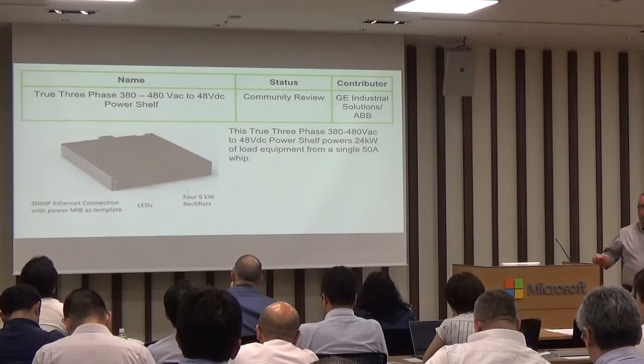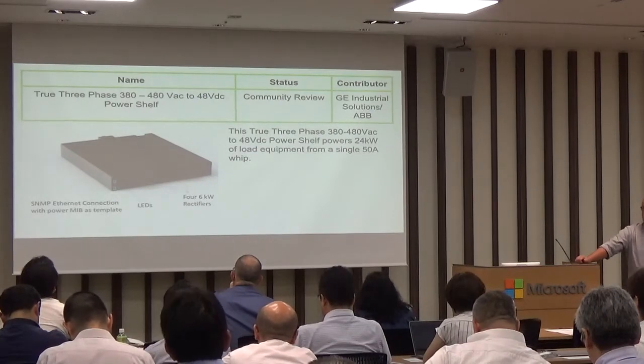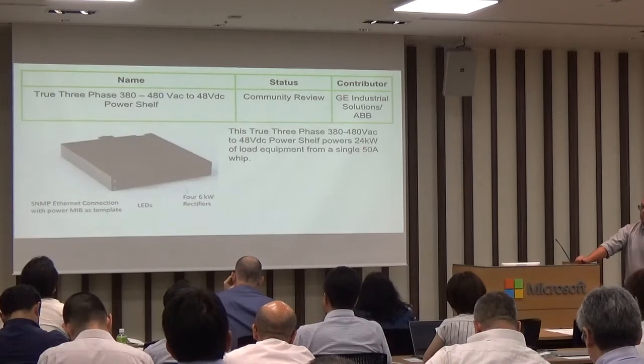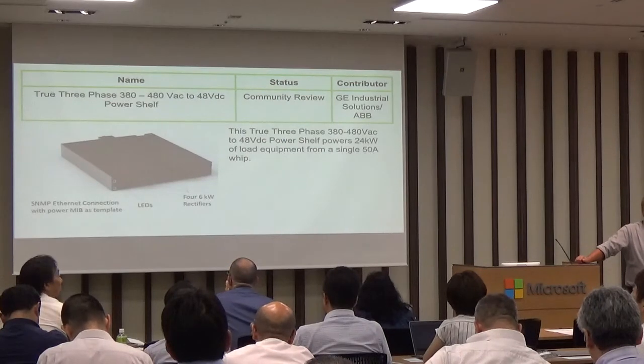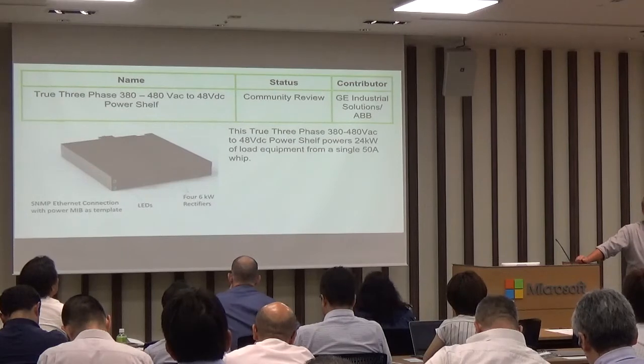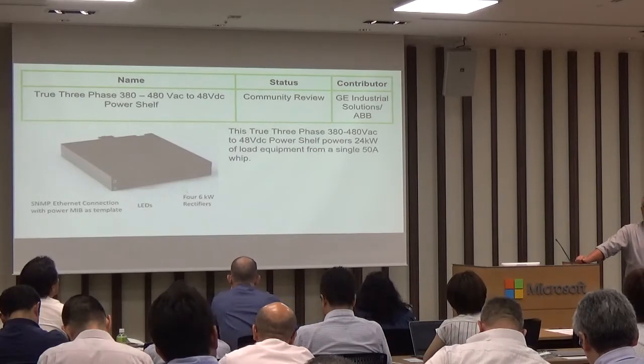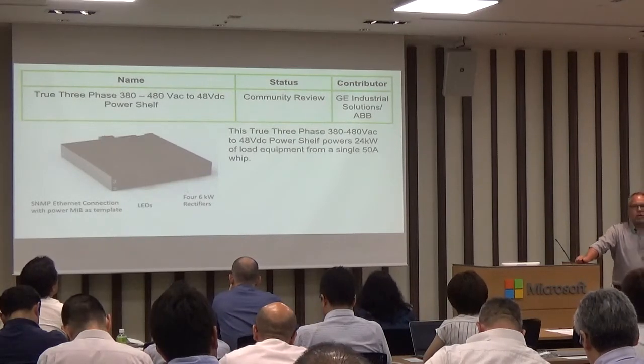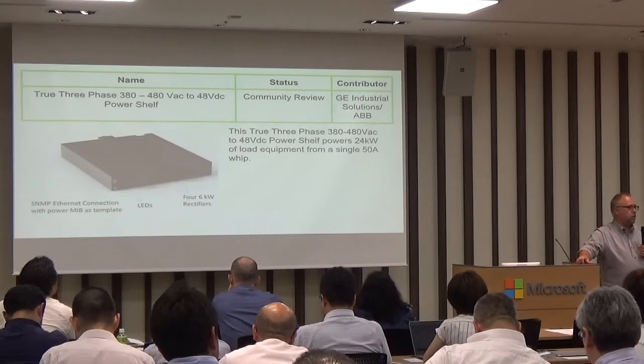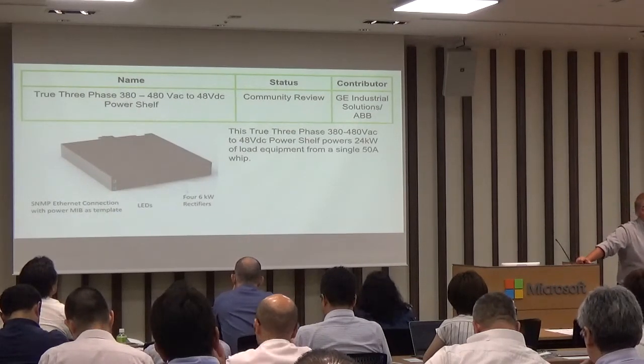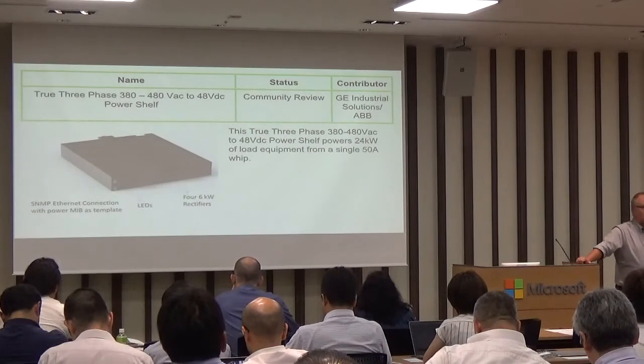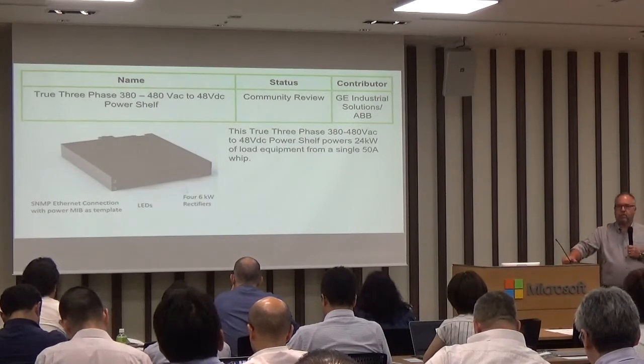This is from General Electric, now ABB: a 380 to 480 volt three-phase AC input. More importantly, it supports a 48 volt DC output. In OpenRack, there are options for the bus bar voltage. The typical bus bar runs at 12 volts—actually 12.5 volts—but there's optionally a 48 volt option.